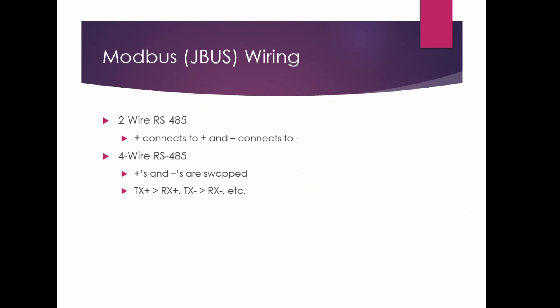For your Modbus or JBUS wiring, on your two-wire make sure your polarity is correct, and same with your four-wire. I've seen where the polarity gets backwards — it generally happens at the gateway end, but it pays to make sure and check it all the way through.